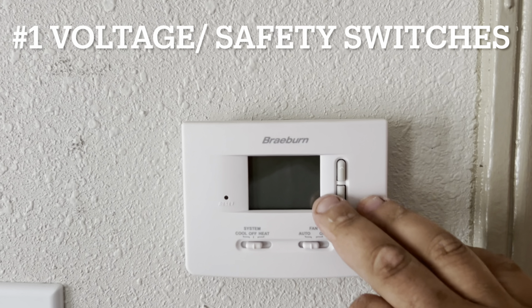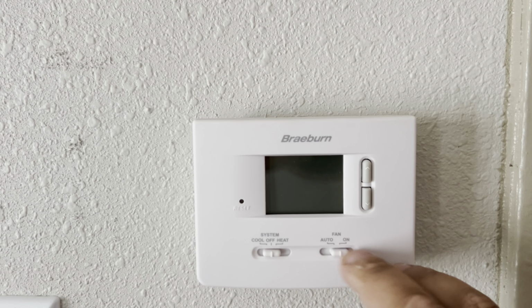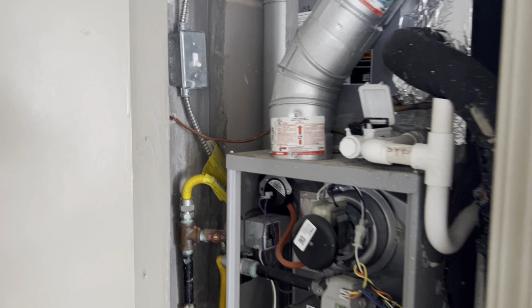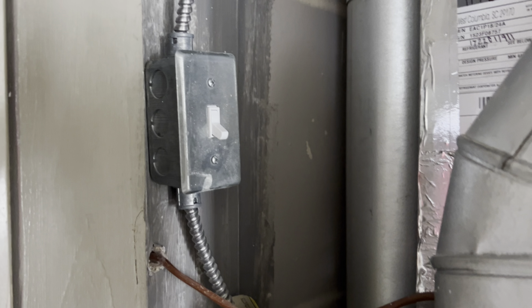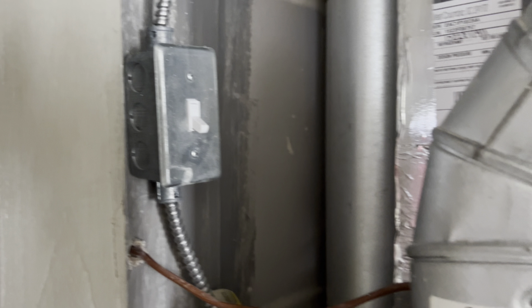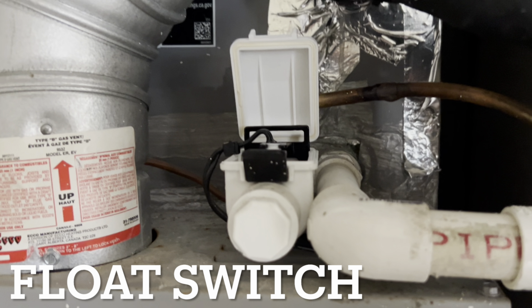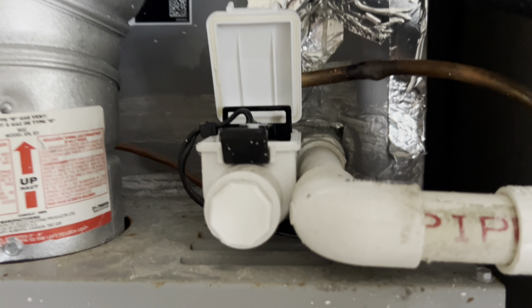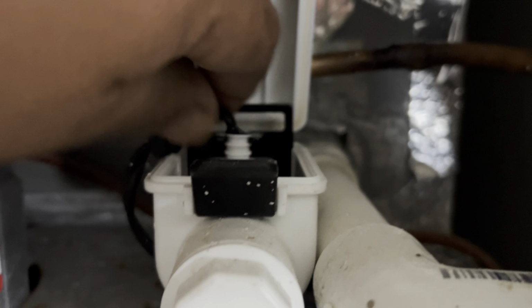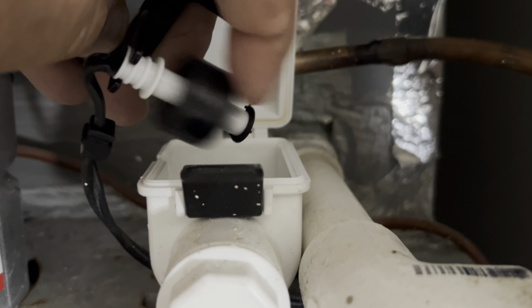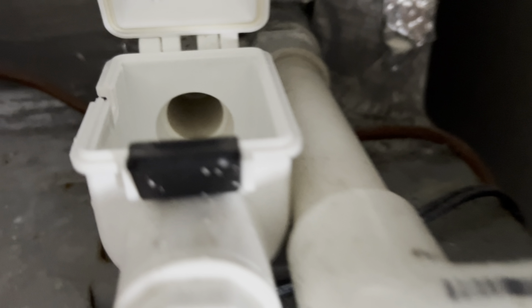If a service call starts off with a thermostat not responding to anything and not lighting up, the first thing to check would be the power switch. Make sure that it is in the on position so the unit can respond. Next to check would be the float switch. This prevents the unit from running if this reservoir here gets filled up with water, and this floater will cut off power to the unit.